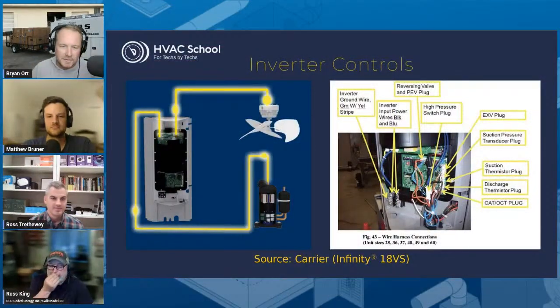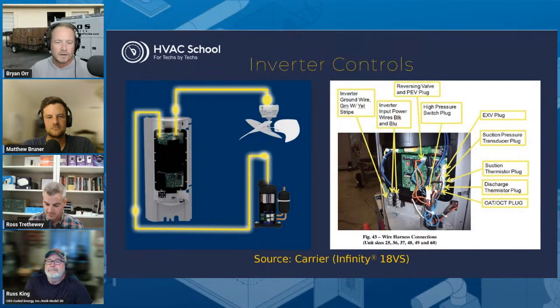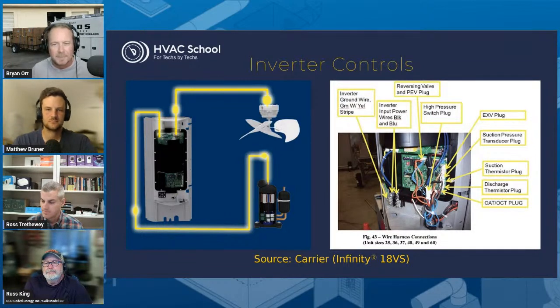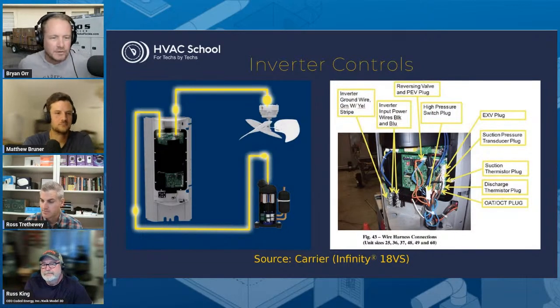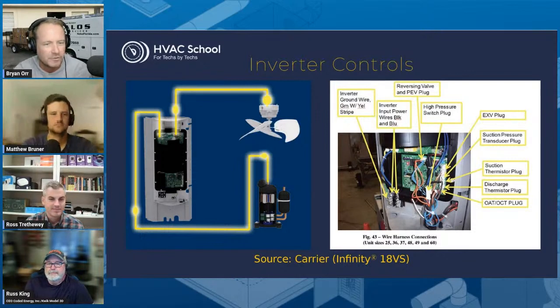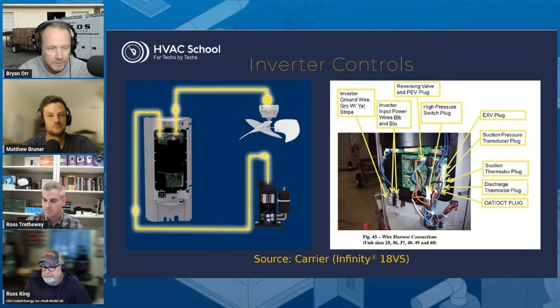I want to go ahead now and move into talking a little bit about some equipment specifics. So maybe some alternate technologies, but I'm just going to give a quick rundown of why, because a lot of people will say, okay, modern heat pumps aren't your granddaddy's heat pump. They're different than they used to be. I just want to talk quickly about why that is, because there's a couple of fundamental reasons that they operate differently. I first want to talk about inverter-driven technology, because I think a lot of people misunderstand what's happening, which is that when it gets real cold outside, you're spinning the compressor faster. That's what you're doing.